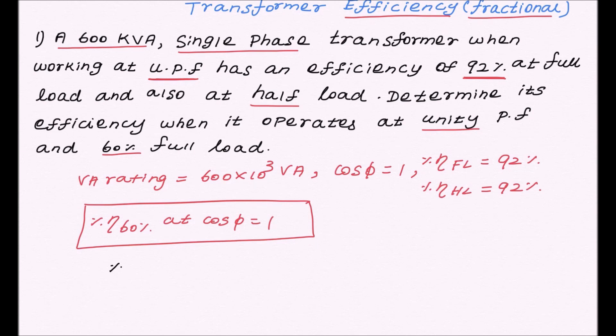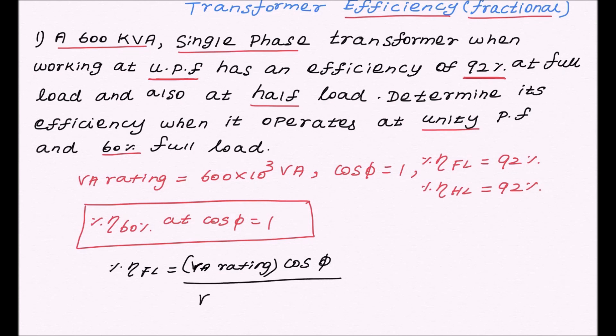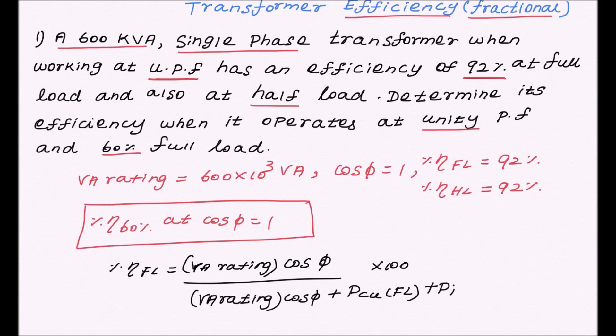The general formula for percentage full load efficiency is: (VA rating × cos φ) divided by (VA rating × cos φ + full load copper loss + iron loss), all multiplied by 100. This is the general formula to calculate the efficiency of the transformer at full load. The data given is that full load efficiency is 92%.